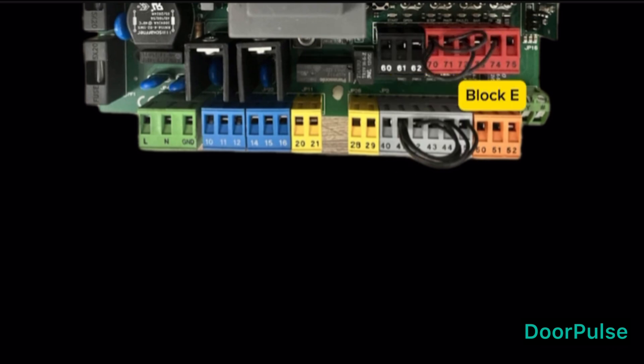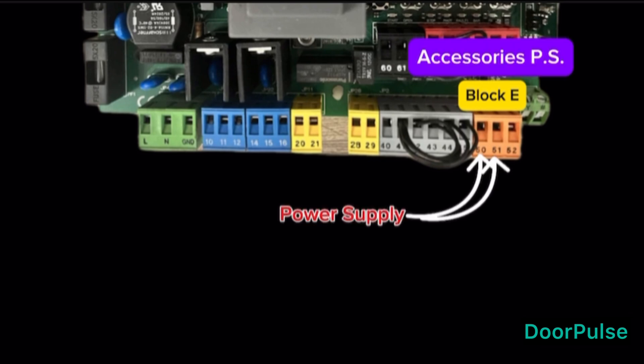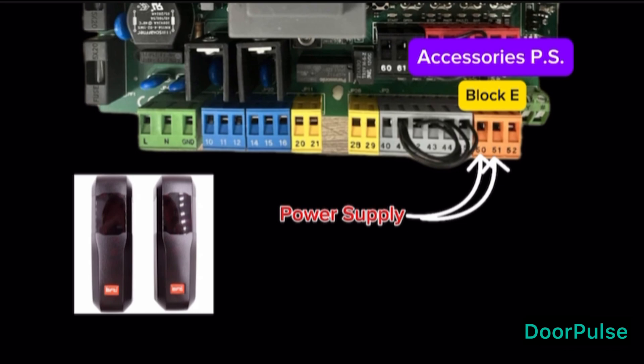Block E, Accessories Power Supply Block. Terminal 50 and 51 is AC power supply. The power supply for photocells. Terminal 51 is 24 volt phase power supply. Terminal 50 is neutral power supply.